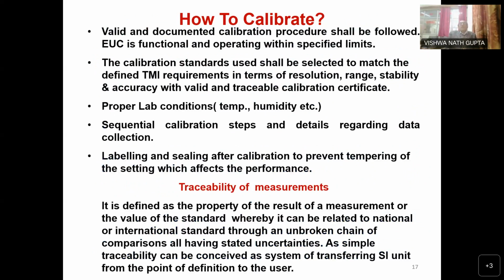Now I am going to explain, sir, why and how to calibrate test equipment, how it should be calibrated. Especially in the electrical field, we do not have any Indian or international standard as in the mechanical calibration field. So here we have to make our own working standards or work instruction manual so that it can serve the purpose of the calibration. That's why valid and documented calibration procedures shall be followed. The EUC, here EUC means equipment under calibration, is functional and operating within specified limits.